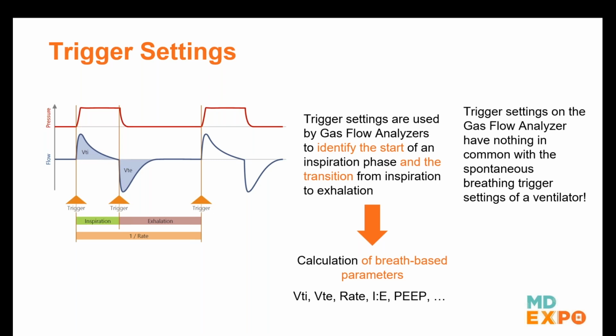Or things like a respiratory rate or the I to E ratio, which is the ratio between inspiratory time and expiratory time, or the PEEP value Kerwin talked about earlier as well. There are many more, and these are also called breath-based parameters. If the ventilator tester, the analyzer, can't tell what is an inspiratory and an expiratory phase, it's not going to be able to calculate and measure all these values. Does that make sense so far? Whenever your device is not triggering, you would just see dashes for these values on your display, or something saying no trigger. And gas flow analyzers typically also have a trigger indicator.